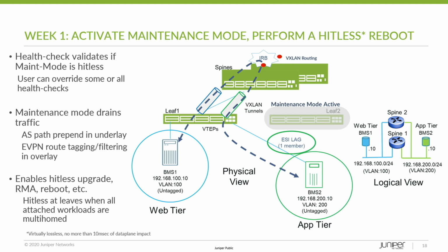The last bullet point there I think is pretty critical. Spines are easy to put into maintenance mode because of the nature of the IP CLOS fabric. It's redundant, doesn't matter which spine you use. Leaves are a fair bit different. If you'll notice leaf 1 and bare metal server 1, there's no way we can take leaf 1 out of the forwarding path and expect that to be hitless, right? It would be unreasonable. So we would fail maintenance mode activation on leaf 1 unless you choose to forcefully override that action, and we'd assume you'd be doing that in a maintenance window.